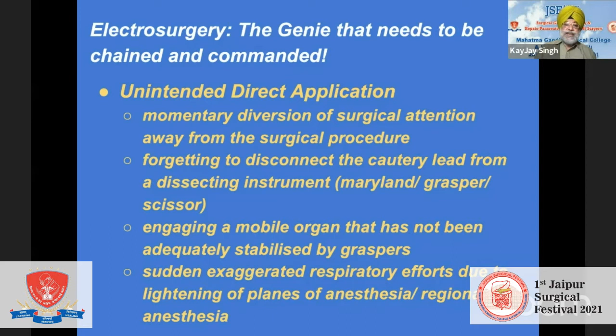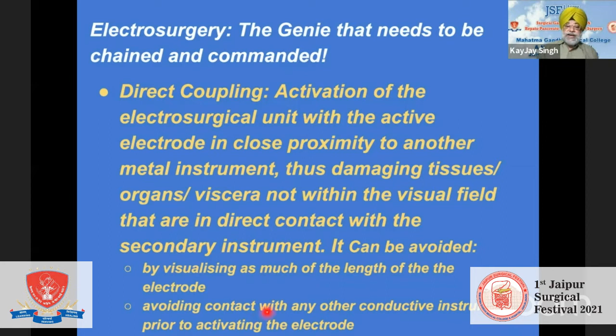The second manner in which the electrosurgical unit can fail is called direct coupling. Direct coupling is the activation of the electrosurgical unit with the active electrode in close proximity to another metal instrument, thus damaging tissues, organs, viscera not within the visual field that are in direct contact with the secondary instrument. It can be avoided by visualizing as much of the length of the electrode as possible on the monitor. So the shaft of the active energy delivering instrument should be in vision, avoiding contact with any other conductive instruments prior to activating the electrode.